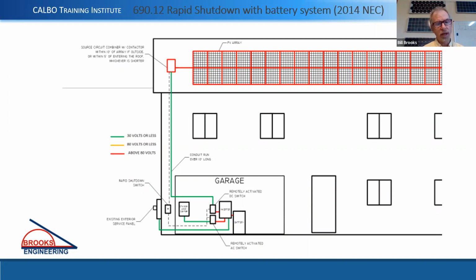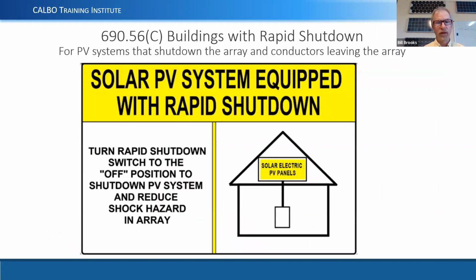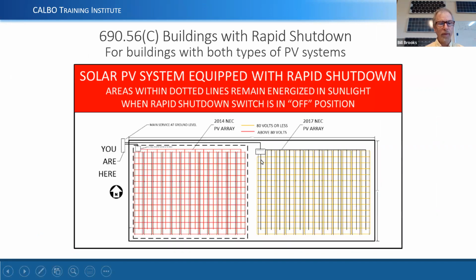and things like that that were part of the system would be considered part of the PV system. In the 2017 code, what we did is we pared down the definition of what a photovoltaic system was to just the power producing system. And so when we apply rapid shutdown to the PV system, it does not include the energy storage system. That being said, the energy storage system has its own requirements for disconnects and external shutdowns and things like that. And so we can get into those details as well. So there's our sign for rapid shutdown with PV systems. If we happen to have a building, this often happens more with commercial buildings than it does with residential, but occasionally in a large residential, we can increase the size of the system.